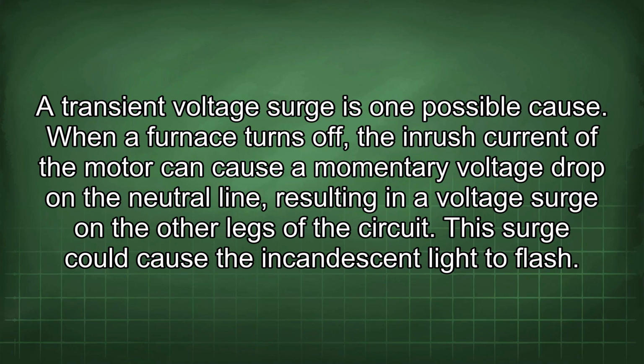Transient voltage surge is one possible cause. When a furnace turns off, the inrush current of the motor can cause a momentary voltage drop on the neutral line, resulting in a voltage surge in the other legs of the circuit. This surge could cause the incandescent light to flash.